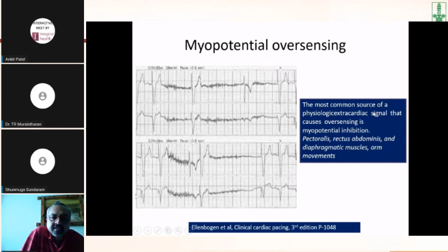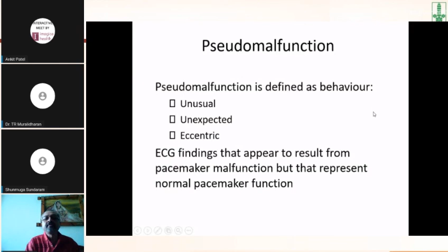So the most important thing, as I said earlier, is that true malfunction is rare in modern pacemakers. It's most often a pseudo malfunction, wherein it's a false malfunction. It's an unusual, unexpected, and eccentric behavior of the pacemaker. The ECG findings appear to result from malfunction of the pacemaker, but they represent normal pacemaker function. One of the important things which has been pointed out by both the previous speakers is application of a magnet on top of the pacemaker, which can alter the behavior of the pacemaker.